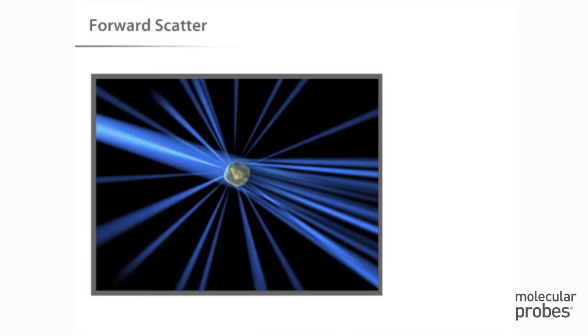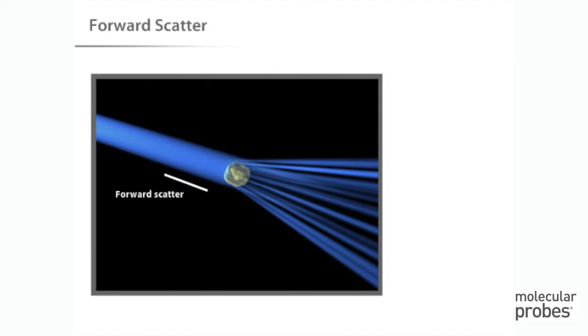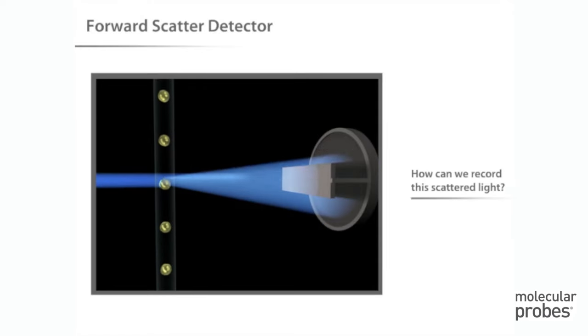As a cell passes through the laser, it will refract or scatter light at all angles. Forward scatter, or low angle light scatter, is the amount of light that's scattered in the forward direction as laser light strikes the cell. The magnitude of forward scatter is roughly proportional to the size of the cell, and this data can be used to quantify that parameter.